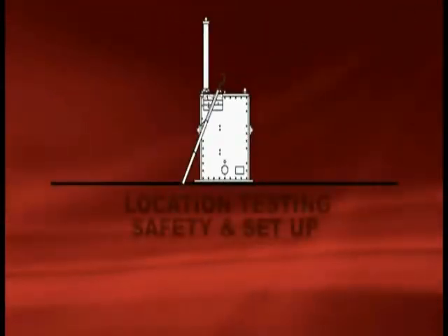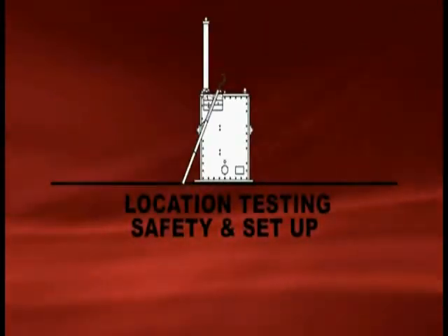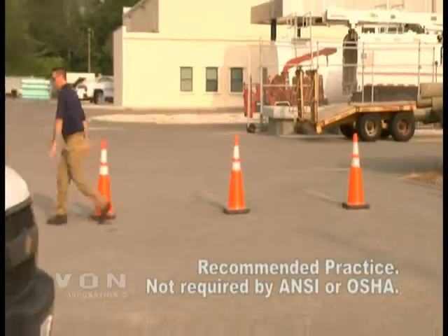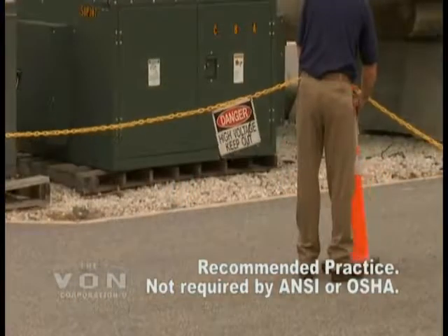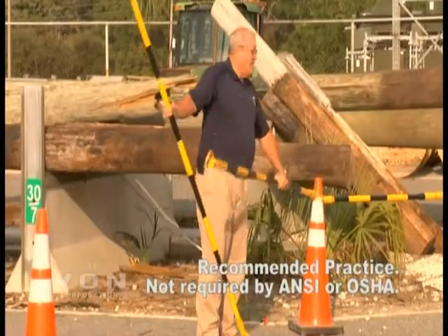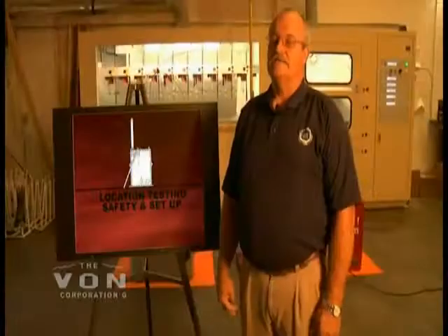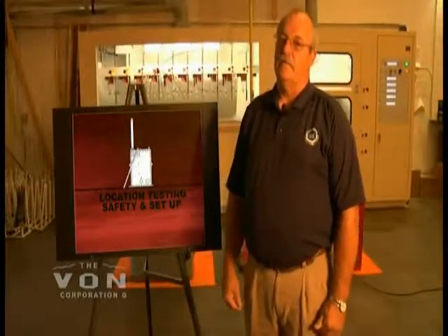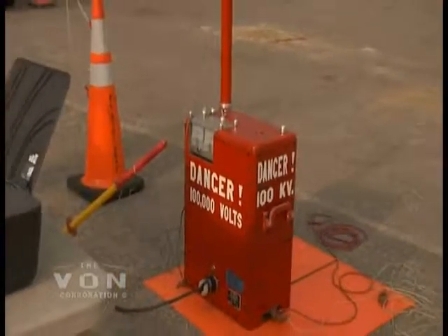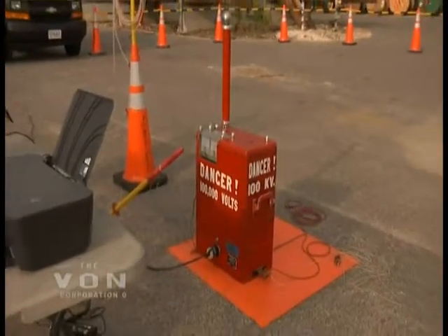When we arrive at the customer's location and they designate our test area, we barricade off the area using road cones and bright yellow chains. This is to help us keep people from walking in while we're testing and accidentally coming in contact with something that may be energized. We set this up around us, and we also visually guard against people coming into the test area. If someone does by chance come in, we just shut the machine off and start the test over.